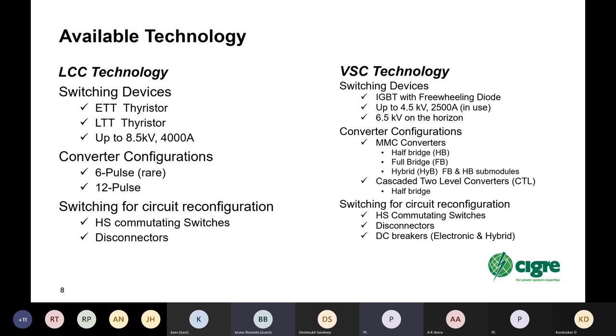Switching for circuit configuration is done with high-speed commutating switches, basically SF6 breakers with auxiliary components to generate current zeros and then allow interruption of DC currents or actually commutation of the current into another path. And of course, disconnectors.